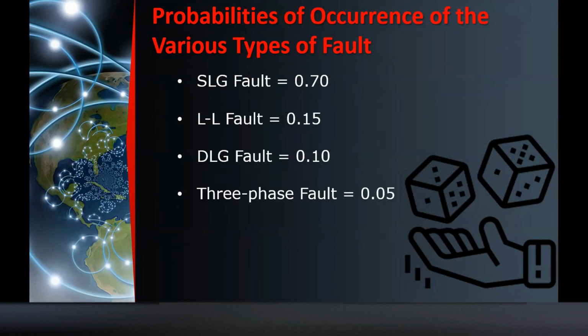So, ang pinaka-common na nangyayari sa power system is the single line to ground fault, which is 70%. Line-to-line fault is 15%, double line to ground fault, 10%, and three-phase fault, 5%. Okay? So, yung three-phase fault, yan ang ginagamit natin sa pagsa-size up ng any equipment. No? Just in case magsa-size up kayo ng mga interrupting capacity. So, minsan, tatandaan nyo rin na minsan nagkakaroon ng time na mas mataas ang single line to ground fault. Okay? So, dapat aware kayo kung ano yung pinakamataas na fault, doon natin isa-size up yung mga protection devices natin. But usually, laging three-phase fault.